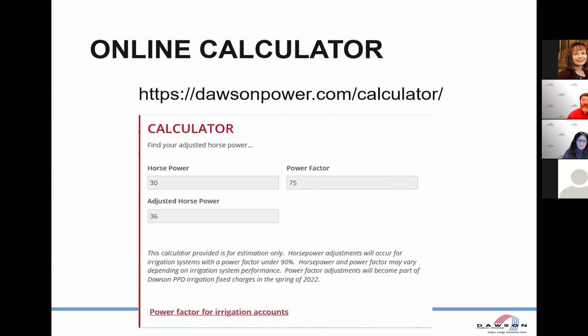In the example down below, this is a screenshot right from the calculator on the website. So you put in what your horsepower is off your bill or off your motor nameplate. You put in what your power factor is that either your manufacturer gave you or you found off of this fall's bill. And we're going to show you the adjusted horsepower right there. So for this particular person with a 30 horse motor and a 75% power factor, their adjusted horsepower is 36 horsepower.